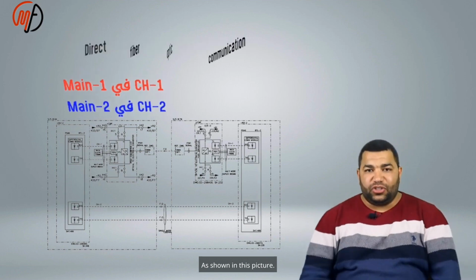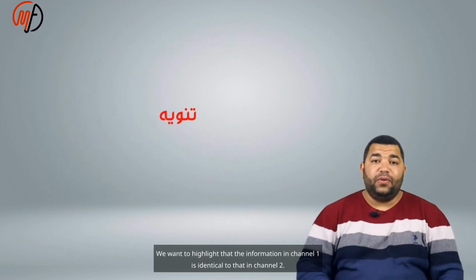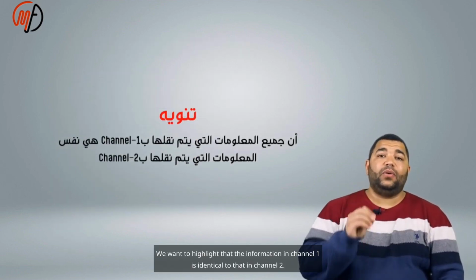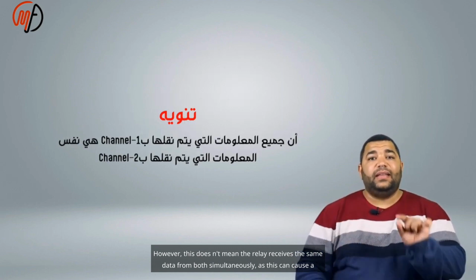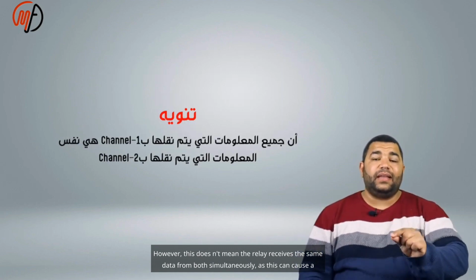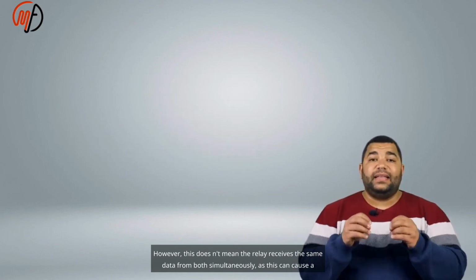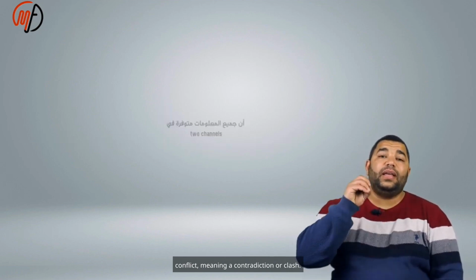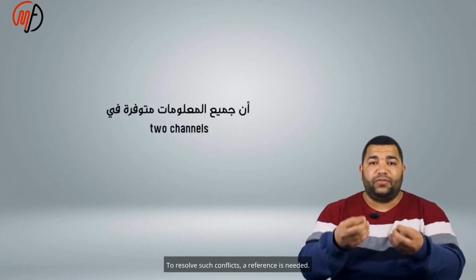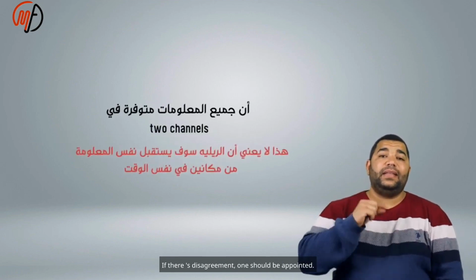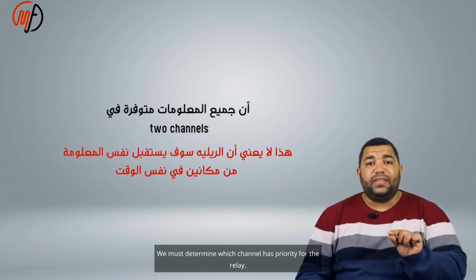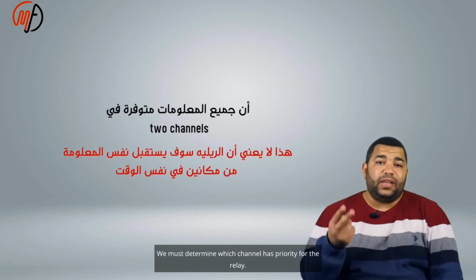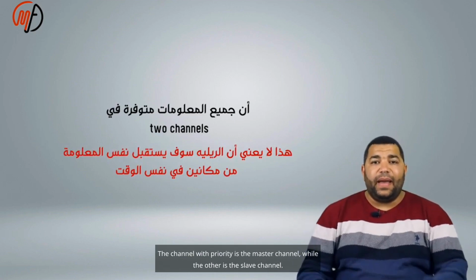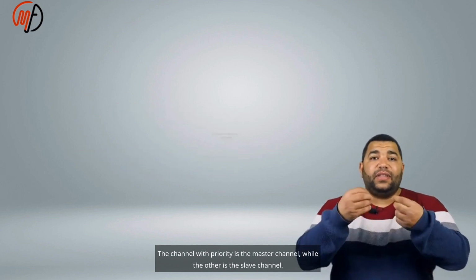As shown in this picture, we want to highlight that the information in channel 1 is identical to that in channel 2. However, this doesn't mean the relay receives the same data from both simultaneously, as this can cause a conflict, meaning a contradiction or clash. To resolve such conflicts, a reference is needed. If there's disagreement, one should be appointed. We must determine which channel has priority for the relay. The channel with priority is the master channel, while the other is the slave channel.